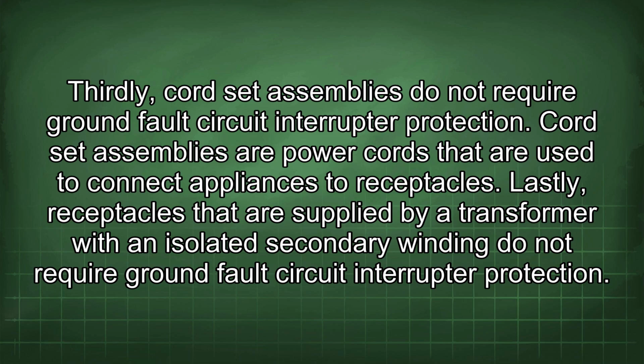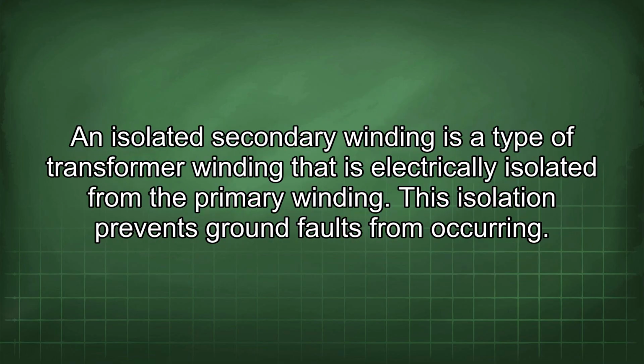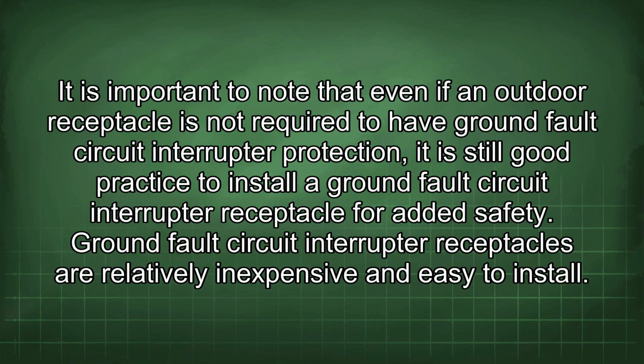Lastly, receptacles that are supplied by a transformer with an isolated secondary winding do not require ground fault circuit interrupter protection. An isolated secondary winding is a type of transformer winding that is electrically isolated from the primary winding. This isolation prevents ground faults from occurring. It is important to note that even if an outdoor receptacle is not required to have ground fault circuit interrupter protection, it is still good practice to install a ground fault circuit interrupter receptacle for added safety.